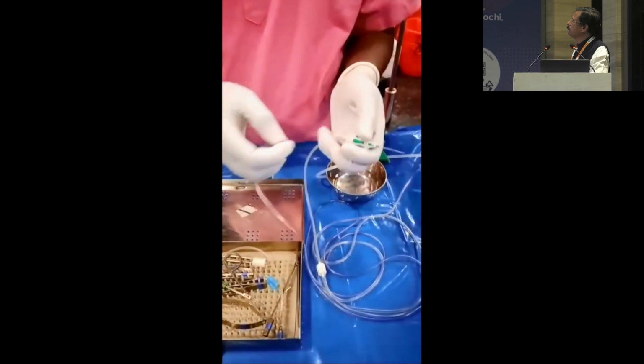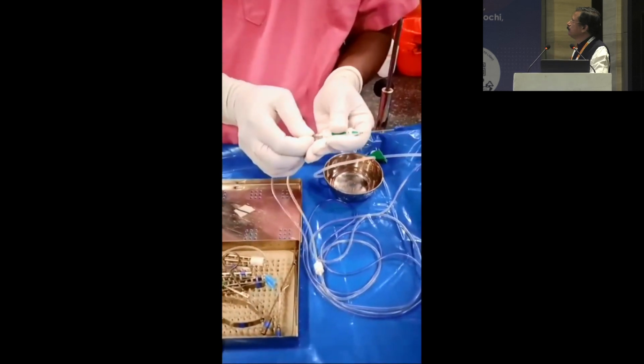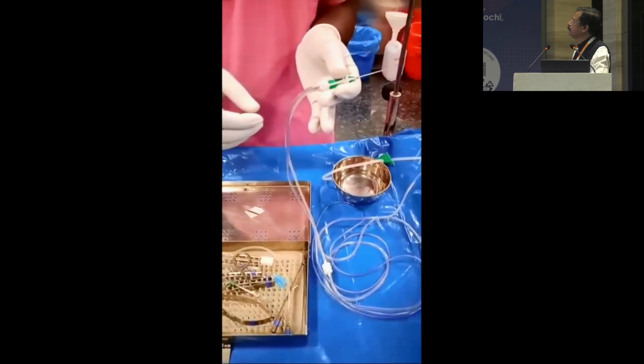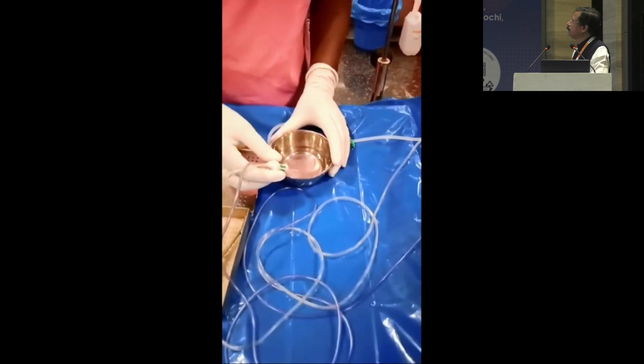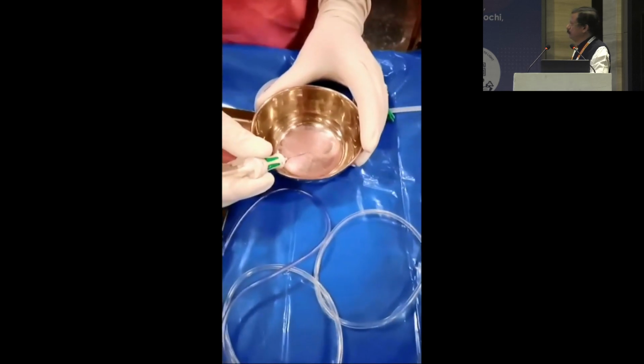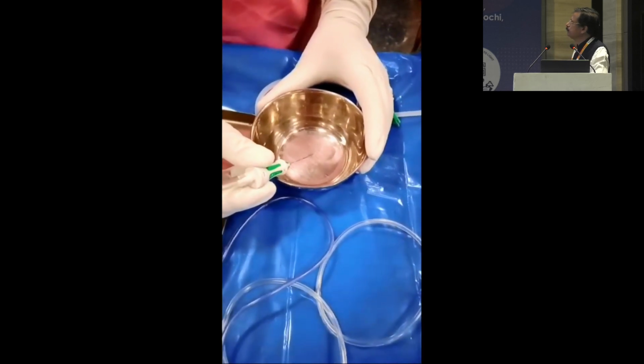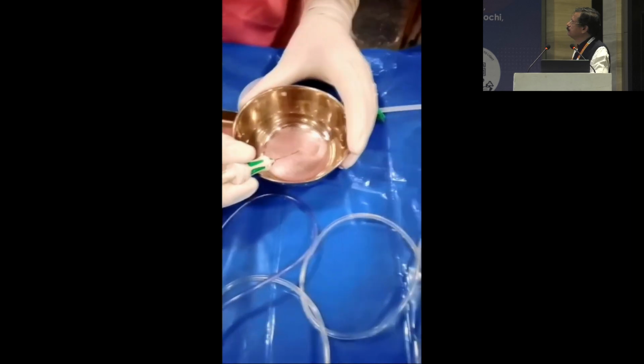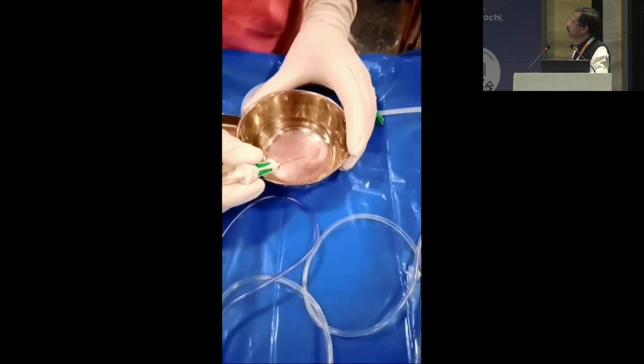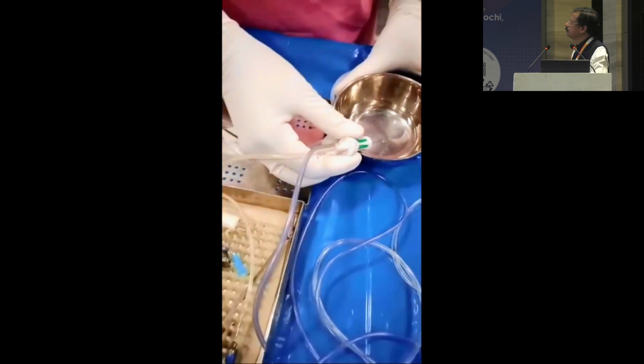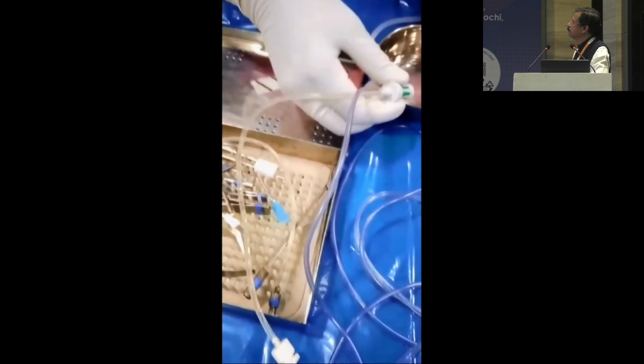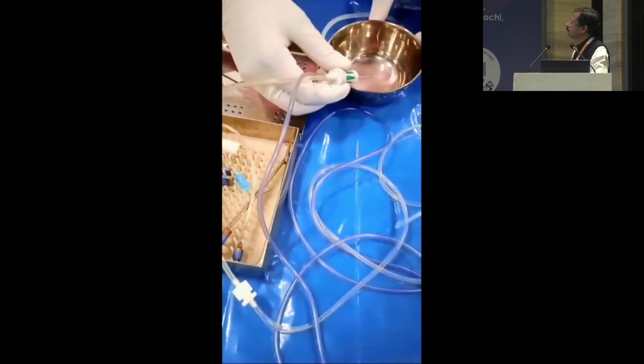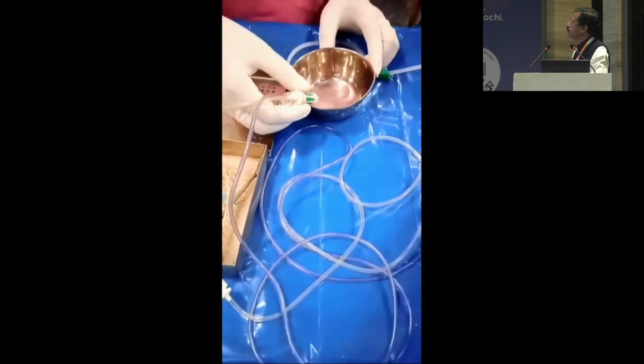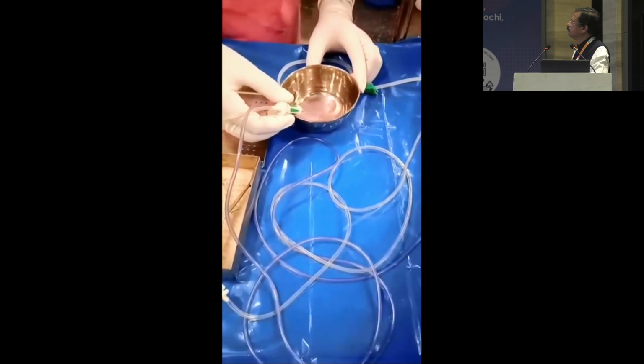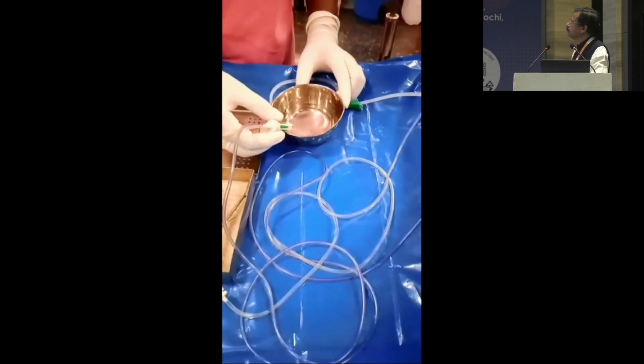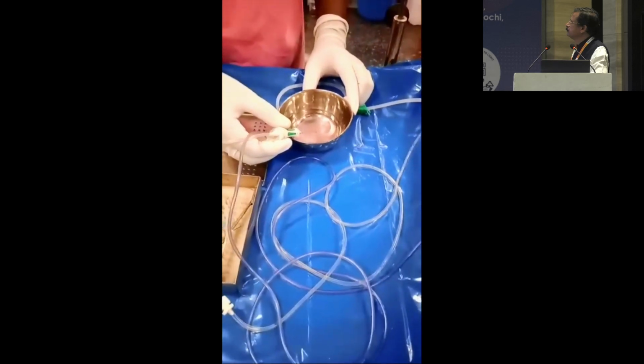Now, how to maintain the anterior vitrectomy machine after the usage? Every time after completion of the anterior vitrectomy, you reconnect the machine, take a bowl, put BSS in there, and put the probe inside and check cutting as well as aspiration. That would aspirate the fluid and also release any clog with the vitreous, viscoelastic or any cortical material. And you should also see the free flow of the BSS in the tubings. That would ensure that any clogging has been cleared.